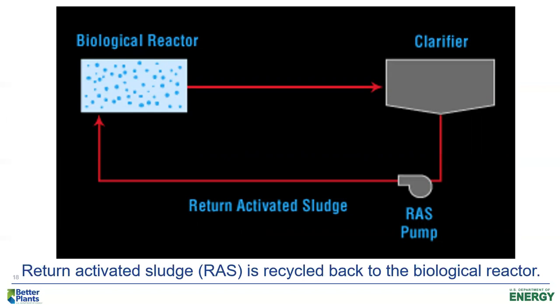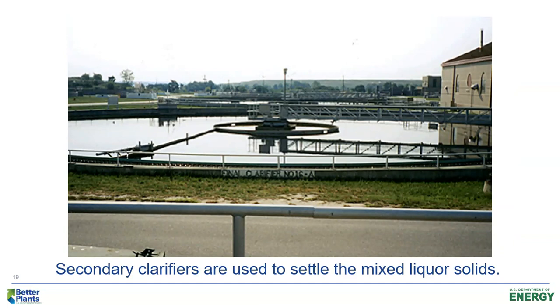Again, the secondary clarifier is extremely important because we have to be able to settle the biomass in order to create a high quality effluent going over the effluent weirs of the clarifier. Now that presents a challenge for us because the specific gravity of the biomass is about 1.05. Specific gravity of water is 1. So that's not a big difference.